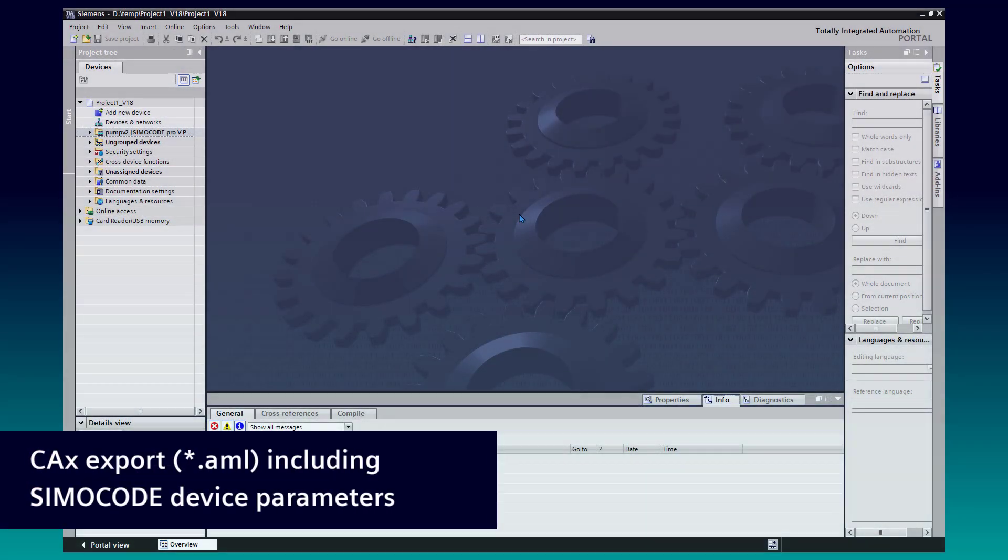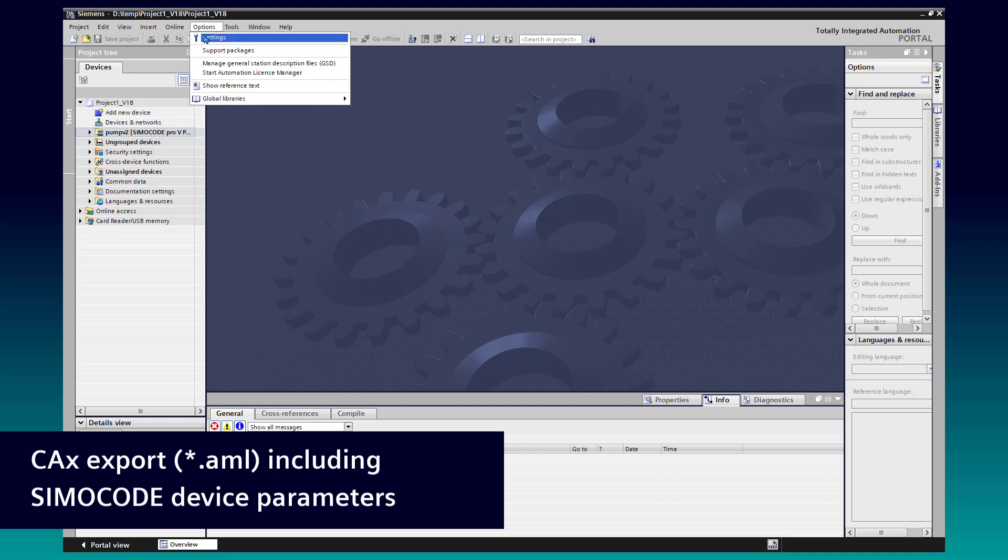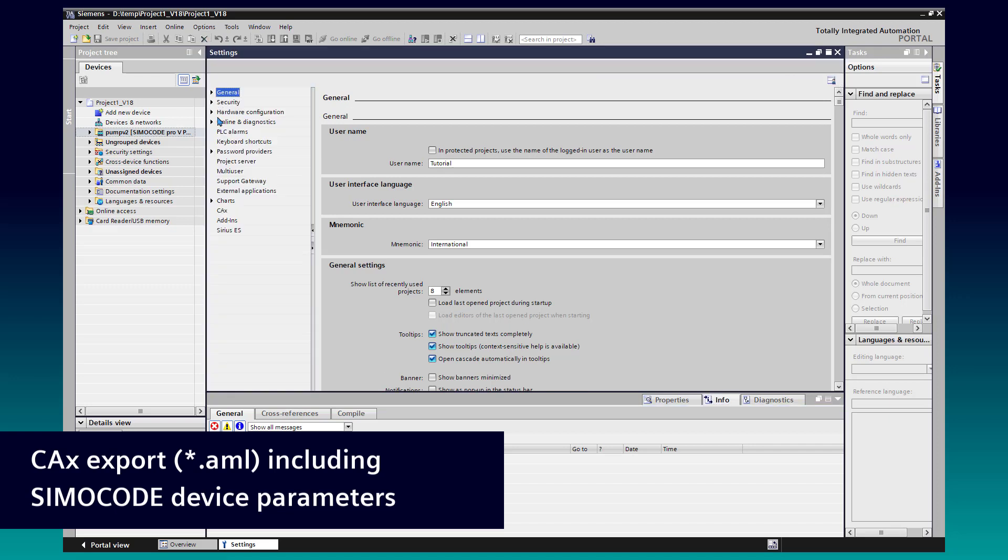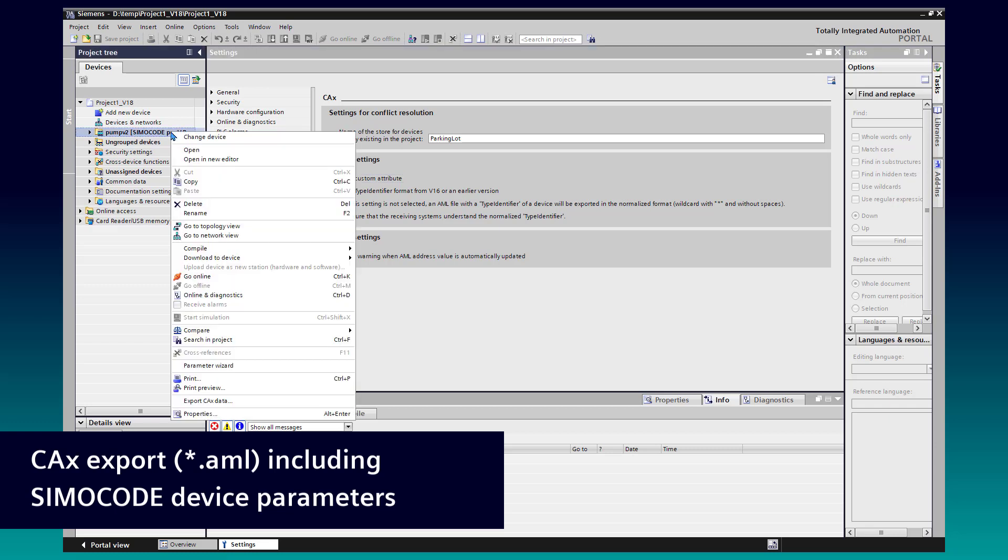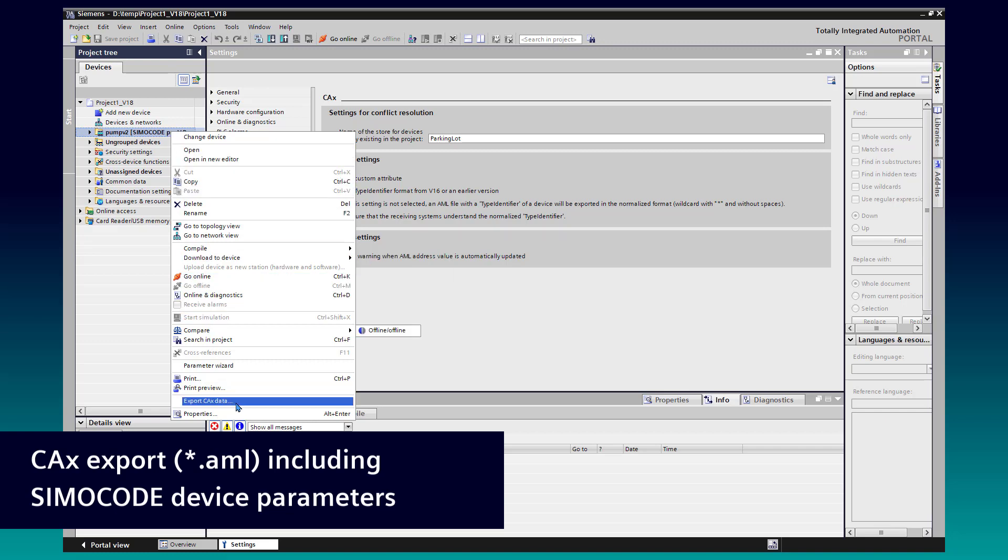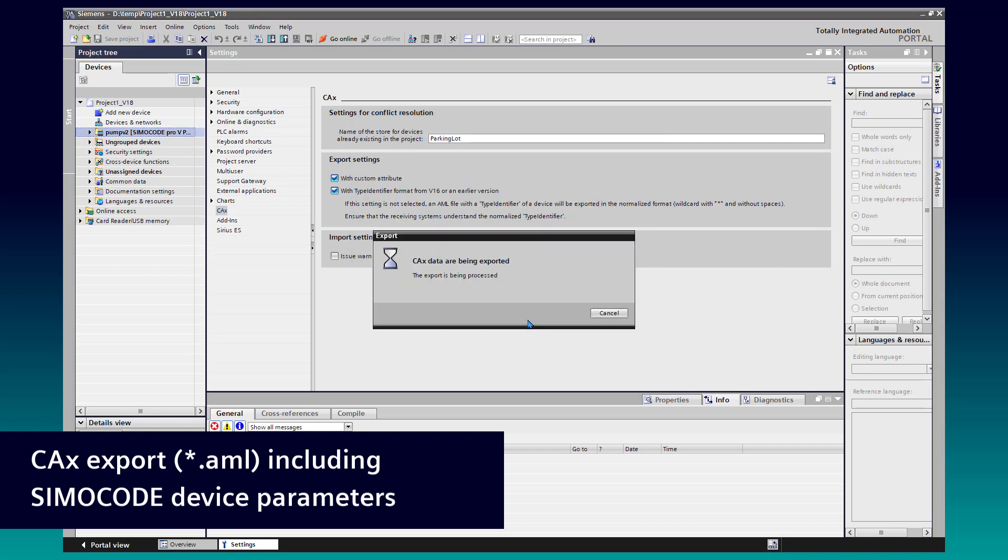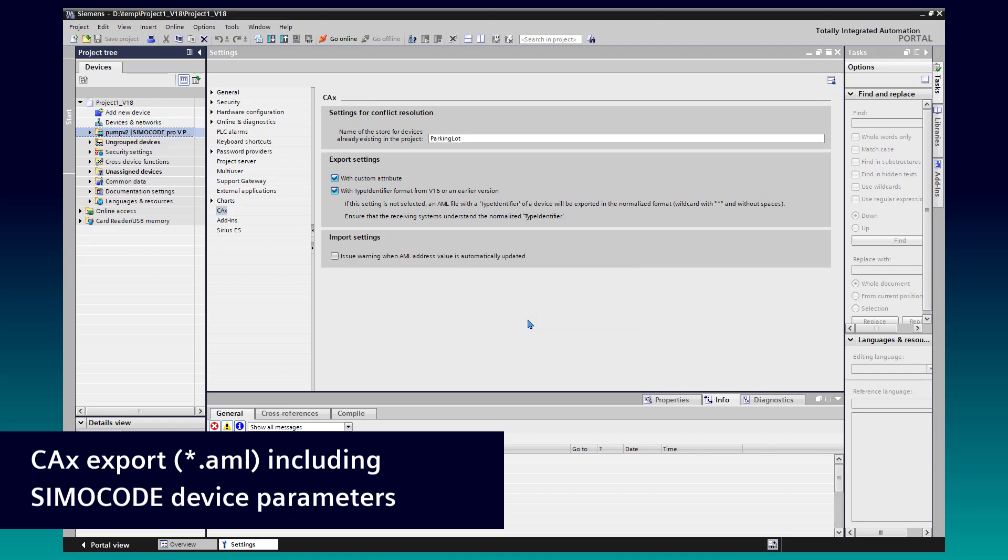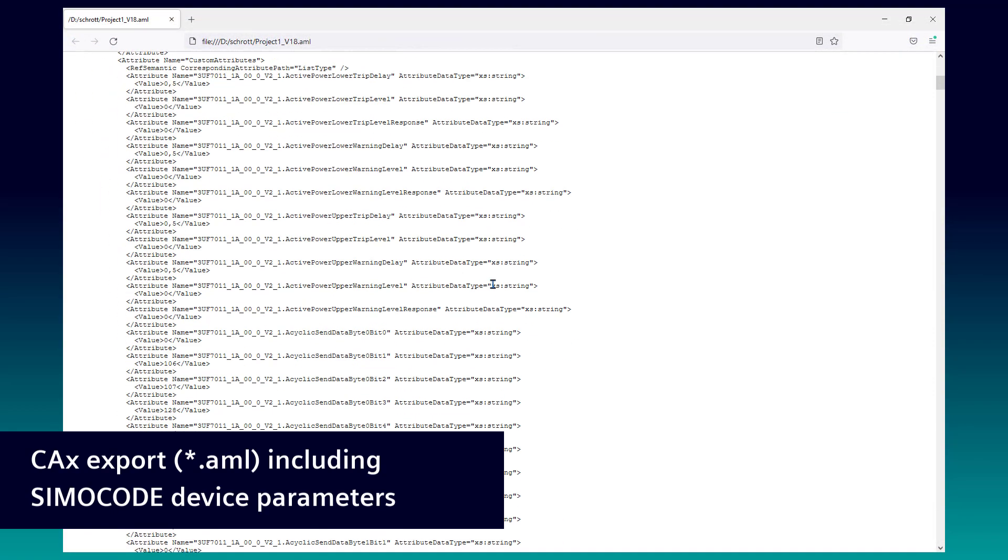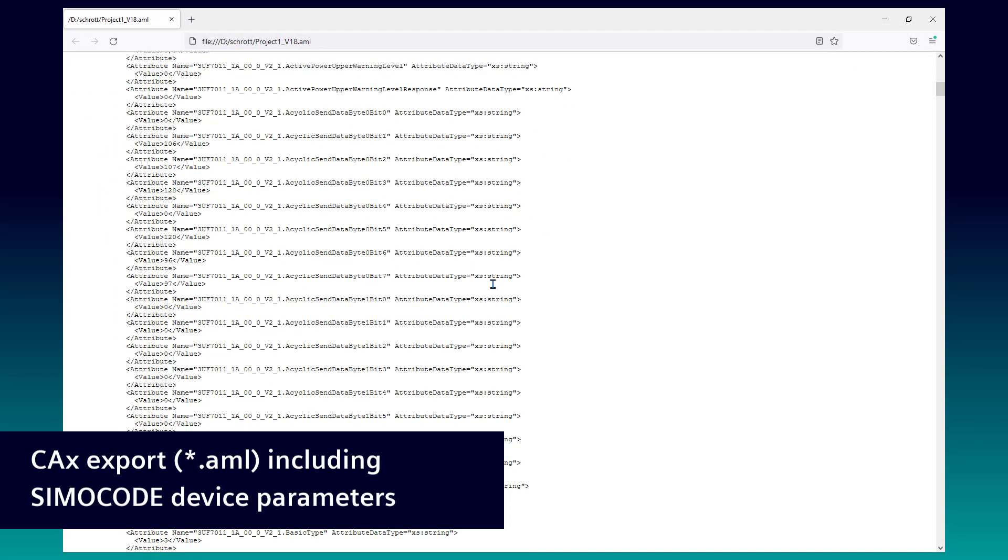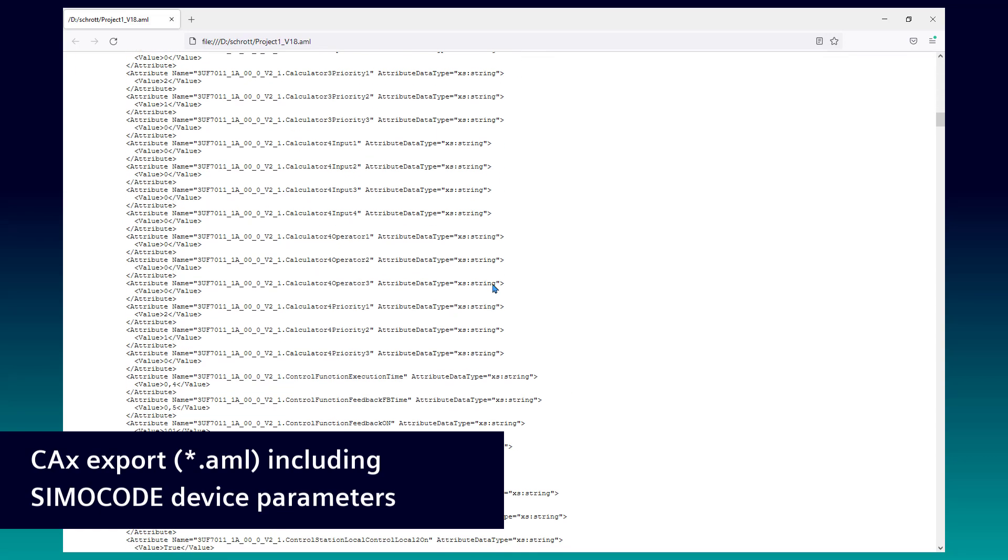With SimoCode ES version 18, it is now possible to export SimoCode device parameters to an AML file. For this, it is necessary to activate custom attribute at the export settings of TIA Portal. With a right mouse click on the SimoCode station and selection of export CAx data, the export will start. The created AML file will include all parameters of the SimoCode device.